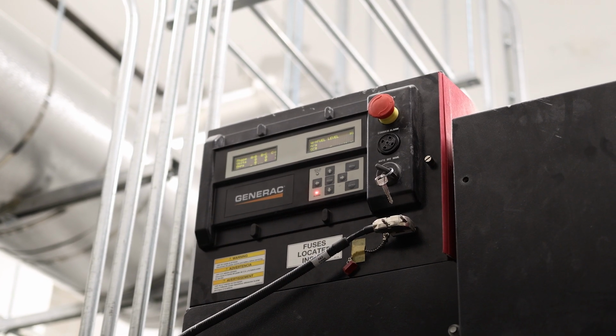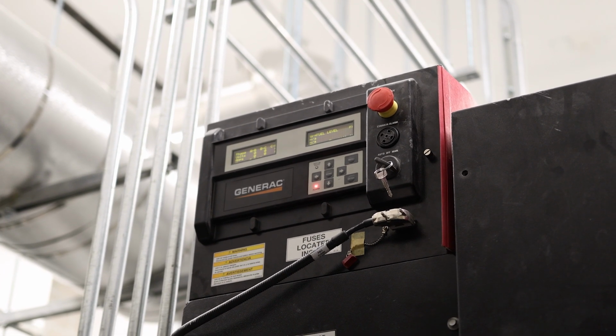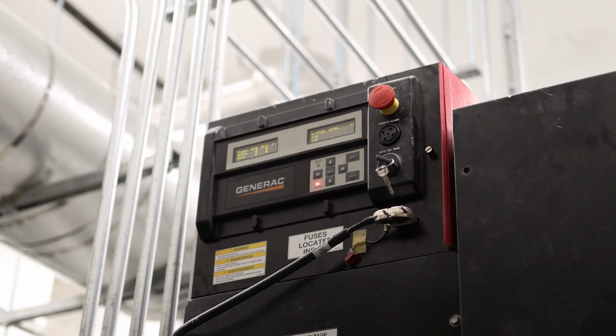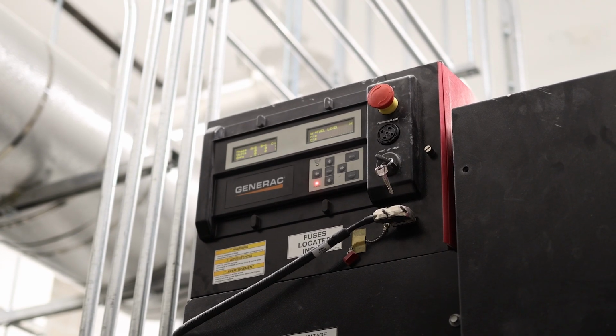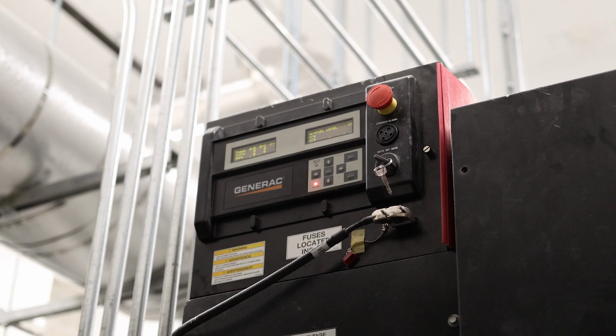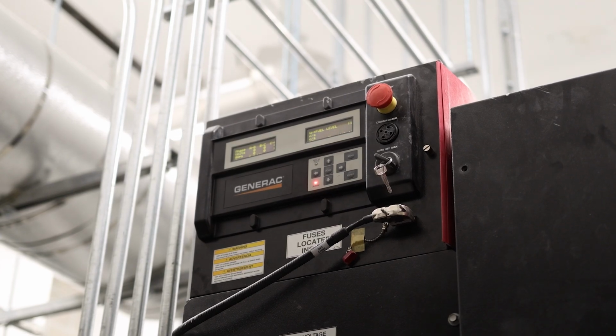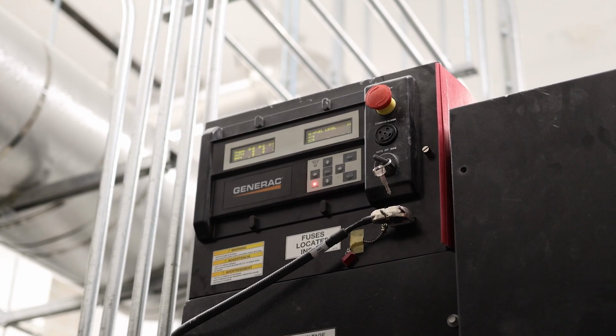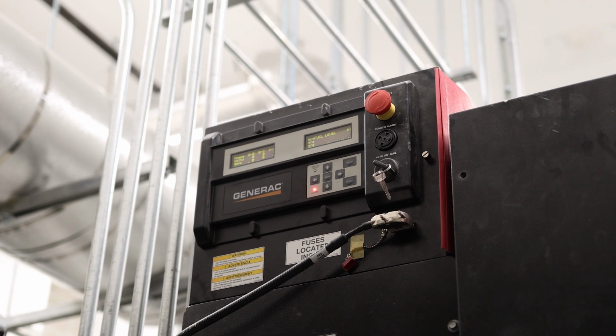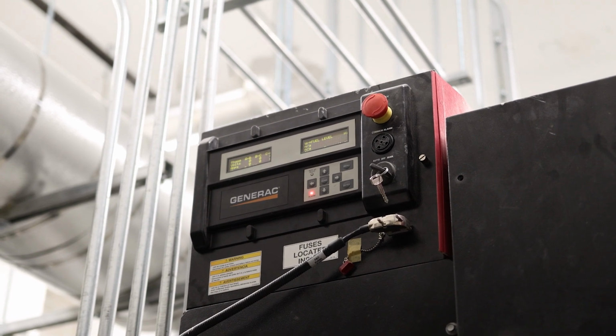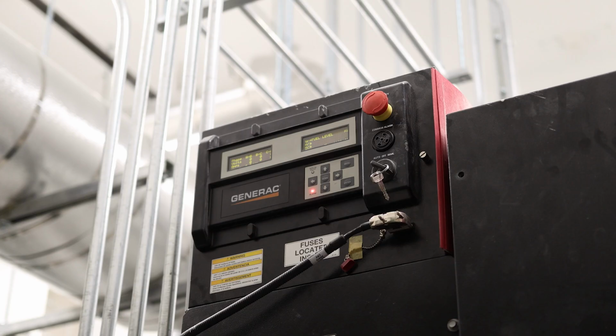Inspect based off of what the alarm may be. If it's low coolant level, when the radiator cools down, check your coolant level, see that it has proper coolant in it. If needed, add a bit. If it shuts down for a high engine temp, take a quick inspection, make sure that the ventilation louvers in the room have opened, stuff of that nature.